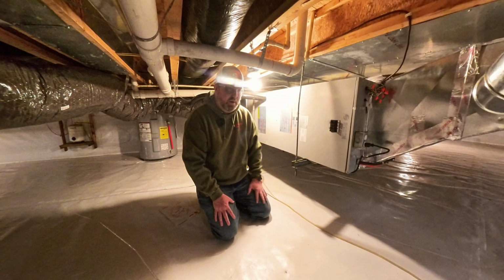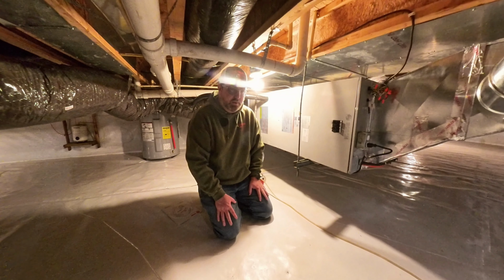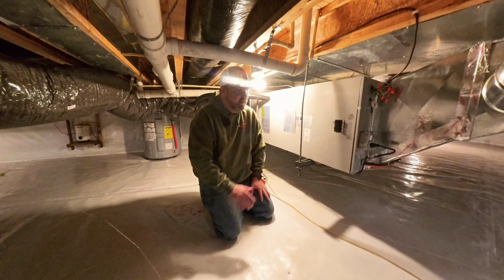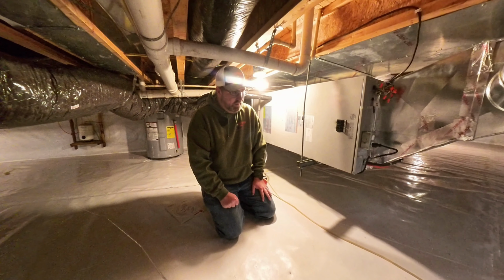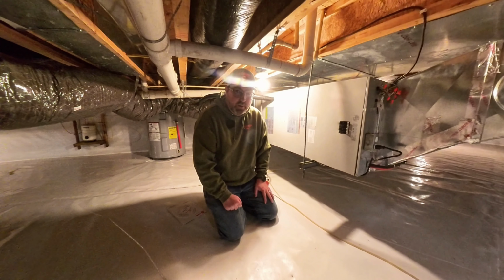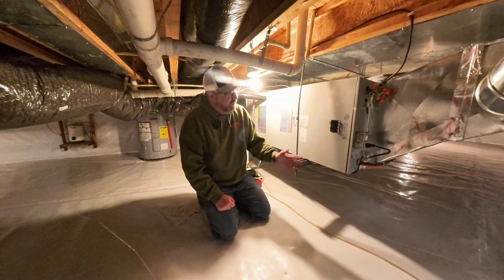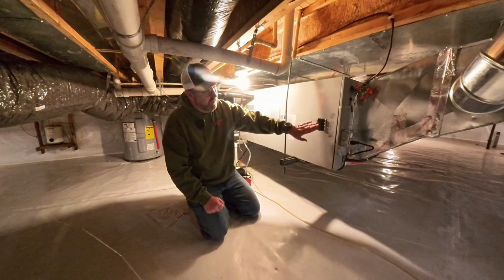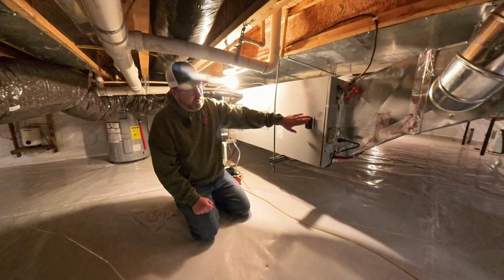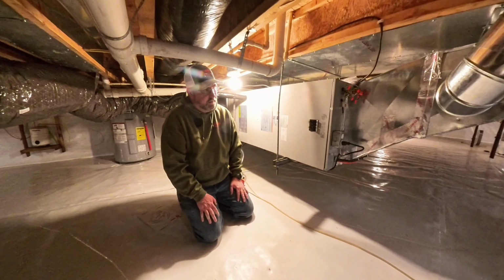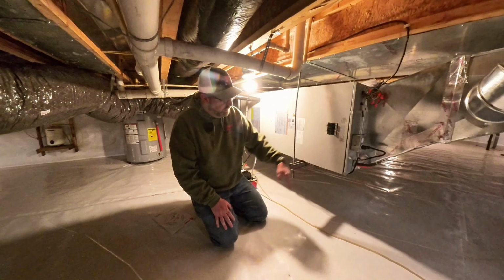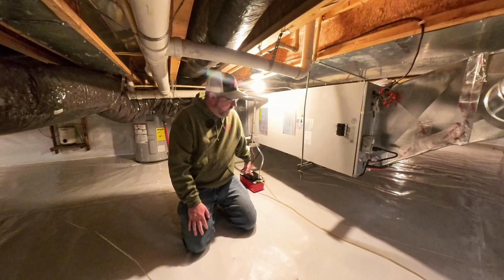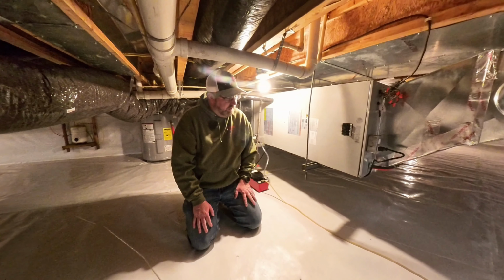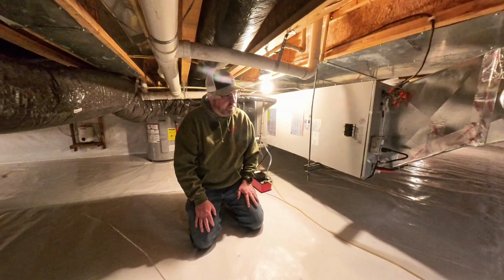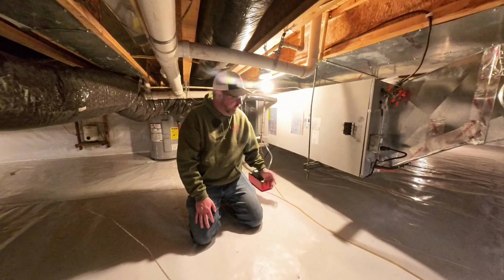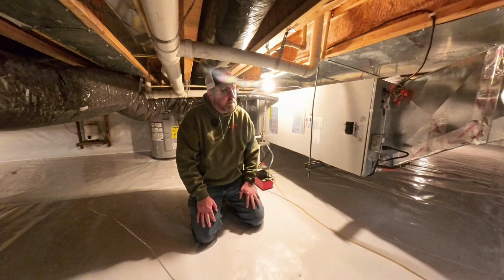I could go to that breaker and actually feel it at the time, and you could feel it humming and hot. So it was definitely on its upper limit. I'm surprised it was not tripping the 60 amp breaker, but we ran a separate circuit for the 5 kilowatt side and hooked the 60 amp circuit back up to the 10 kilowatt side. We added a plug because we replaced the condensate pump. Previously, the condensate pump was just hardwired into the furnace. So serviceability wise, we can unplug that now and change this pump or take it outside if we need to clean it up.